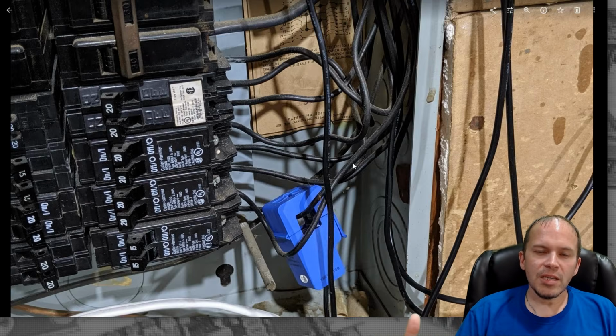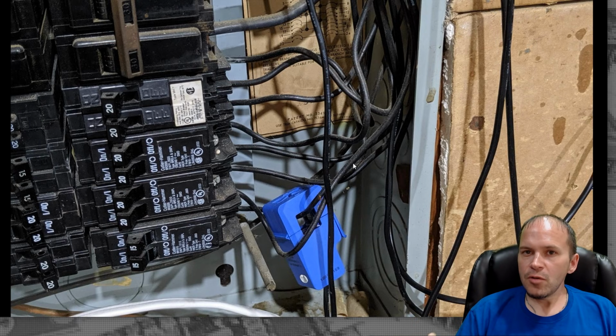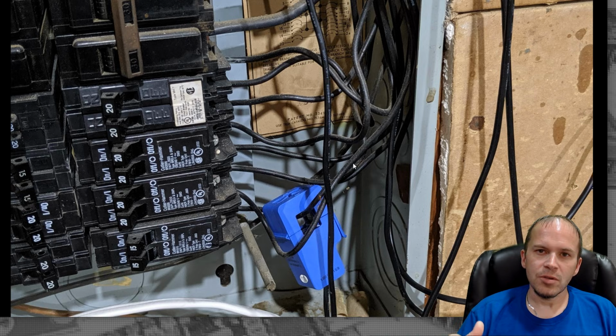Now on your secondary circuits, if you cut the main breaker at the top, you are cutting power down to the bottom of the breaker box. But unless you're very comfortable installing stuff or changing breakers out in your panel or rewiring, I would also have the electrician install the clamps on the circuits you want.